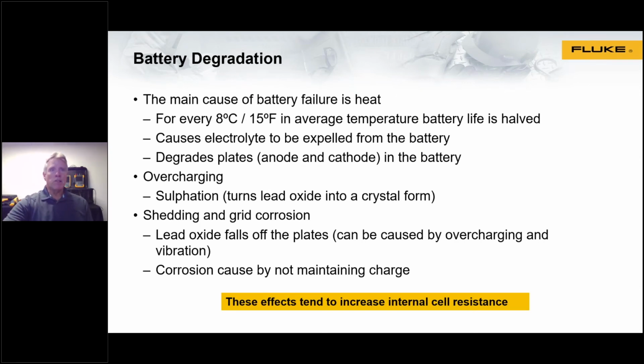Again, keep in mind, main cause of battery failure is heat. Much like a motor, main enemy of motors is heat. So for every increase of about 8 degrees C, average battery life is halved, and it causes degradation in the plates and the loss of electrolyte. Also, overcharging is something that needs to be checked, and this relates directly back to the standards as far as the IEEE standard for what measurements to make and how often to make them. All of these start to cause the phenomena of internal cell resistance changes. So that's why for state of health measurements, battery resistance can tell us a lot about what's going on.